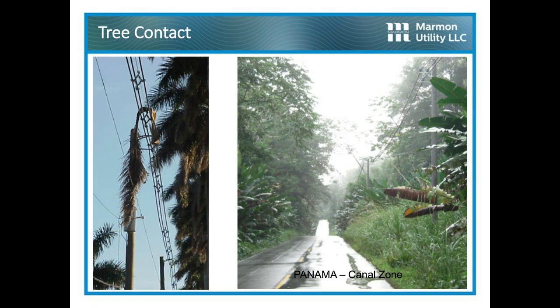This shows just a couple of slides. Again, we have thousands of these slides. The photo on the left shows a palm frond down over a spacer cable line. That's not going to cause an outage. It's not going to cause a problem. You're going to get that on an annual patrol, hopefully knock it off with a hot stick. If you look at the bottom right photo, this is the Panama Canal zone. We're all along the canal, and that's a 35 kV, 34.5 kV transmission line. And there's a lot of concern here for reliability to keep the irrigation pumps on for the canal. Also concern for birds and tree monkeys and these types of animals that cause outages on bare wire systems, not to mention respect for the animals themselves.